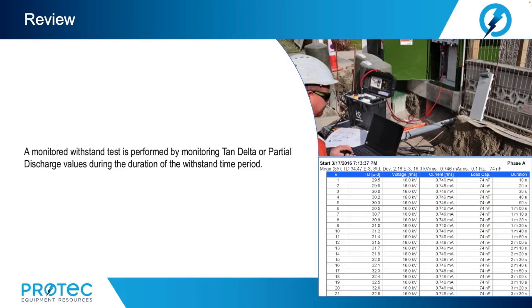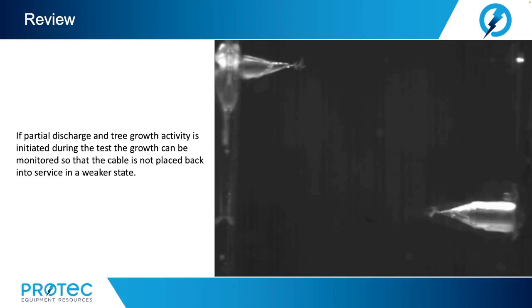But if a channel defect begins to grow, we can either stop the testing immediately, allowing the cable to be put back into service in as close to an as-found condition, or we now can continue to grow the channel independent of time until the channel breaks through, and now we can locate the fault and render necessary repairs. Again, the main advantage of the monitored test is we are no longer at the mercy simply of a stopwatch or a prescribed time period. We actually have the ability to view and witness defects growing in the cable system. If partial discharge and tree growth activity is initiated during the monitored test, the growth can be monitored so that the cable simply is not placed back into service in a weakened condition.